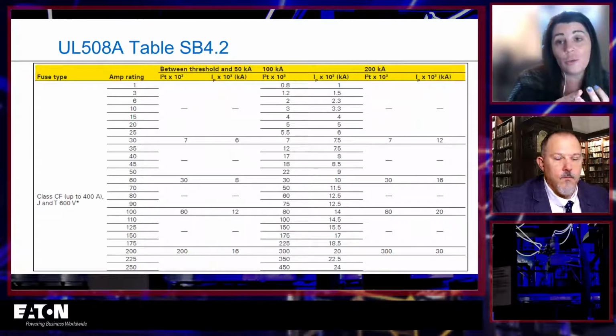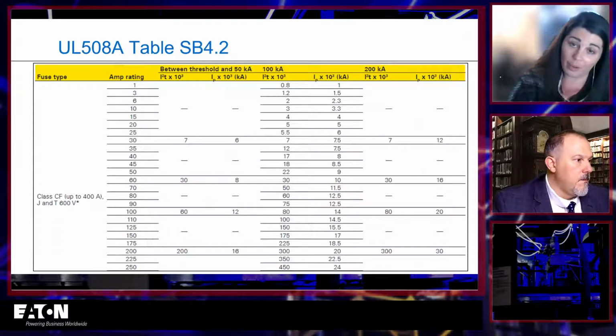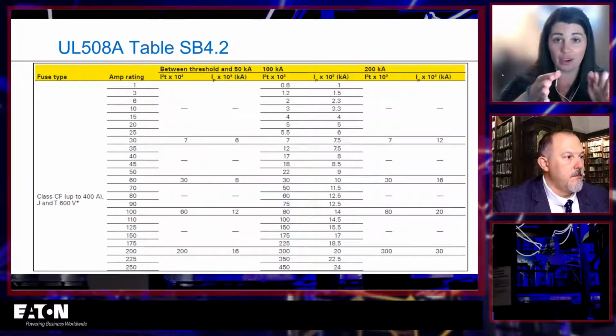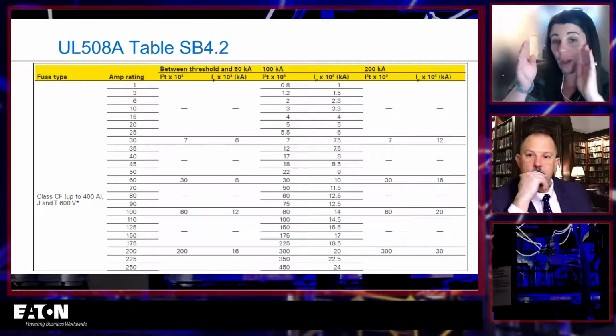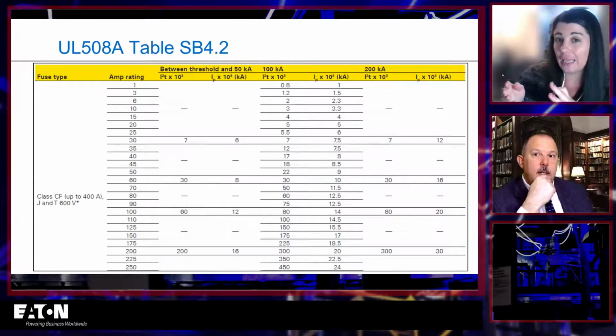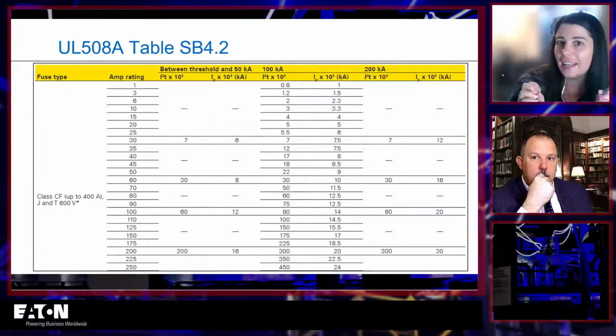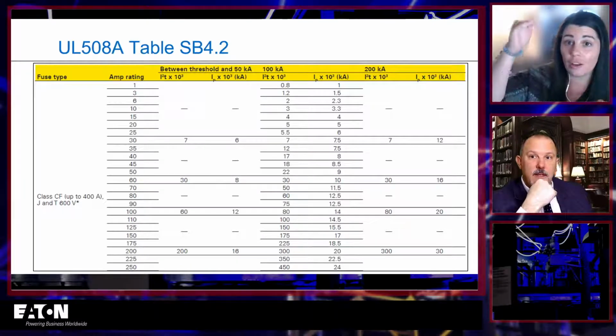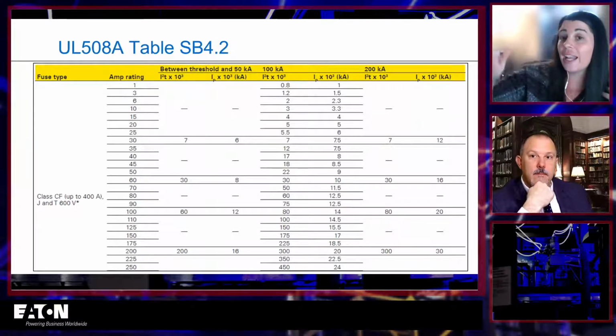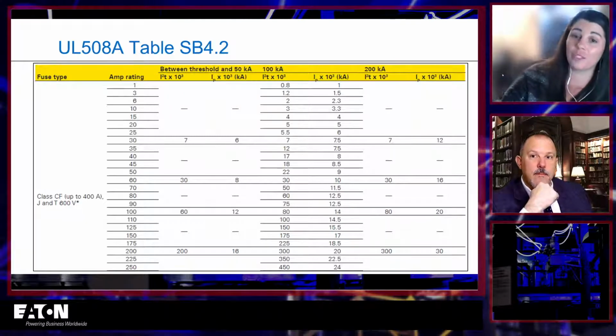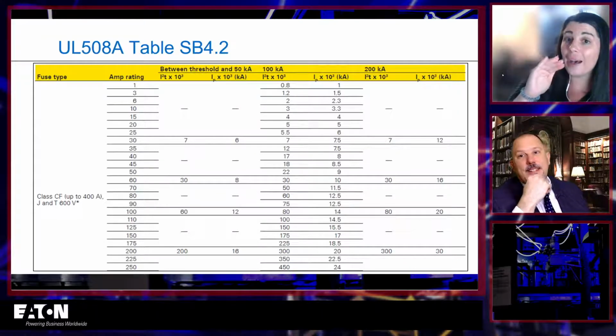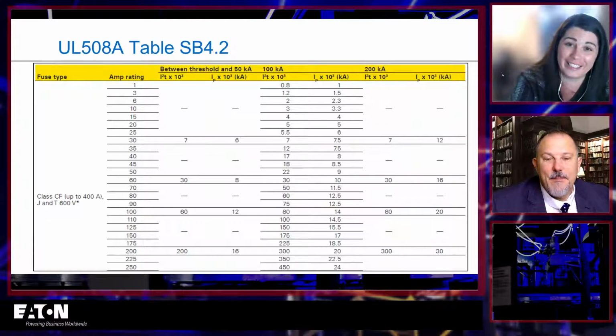So sometimes you run into what I call a sweet spot scenario where, say, your piece of equipment is rated 5 kA, and you have a breaker inside of it that's 10 kA, and your available fault current is 8 kA. That is an application where you might be able to install a current limiting fuse that can reduce the available fault current lower than the 5 kA that the equipment's rated to. And because the interrupting rating of the breaker inside is already 10, you can raise it to above the 8. That's a good point. That's a rare situation, but that's a good point.